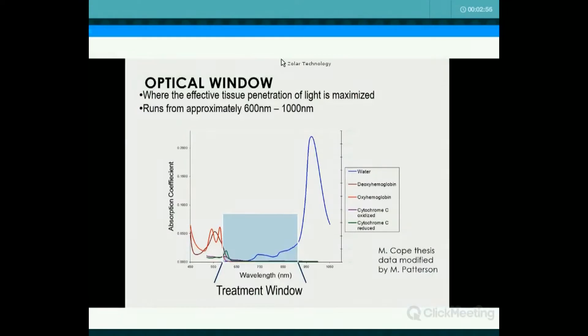When we're talking laser, we've got an optical window — basically from about 600 up to about 910 nanometers. In that area you get less water absorption. If the water was absorbing the laser light, there'd be less cellular effect. This is why we picked the 810 nanometer wavelength, because there's very little water absorption at that wavelength.